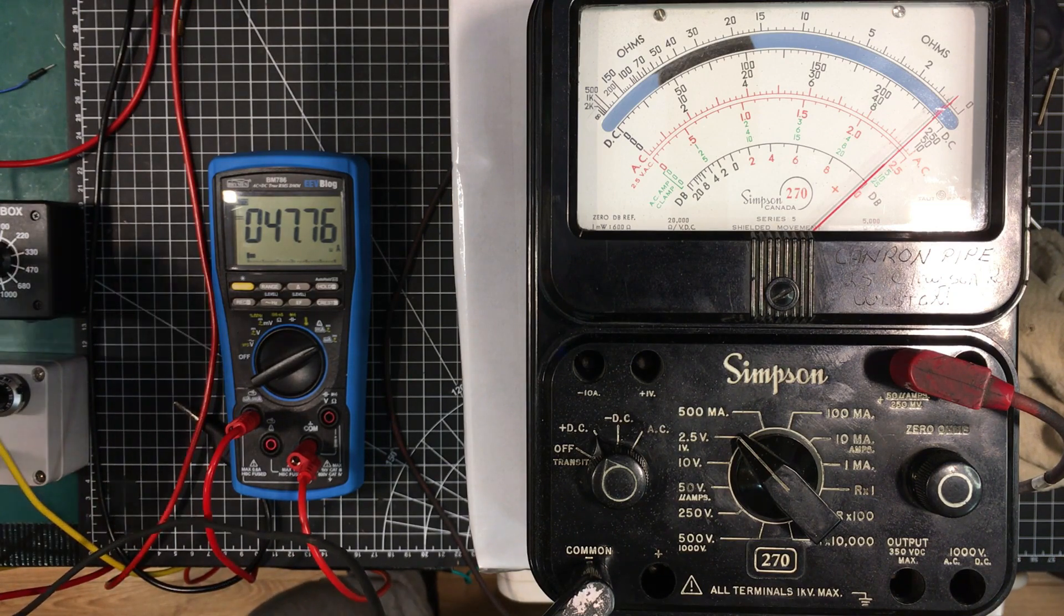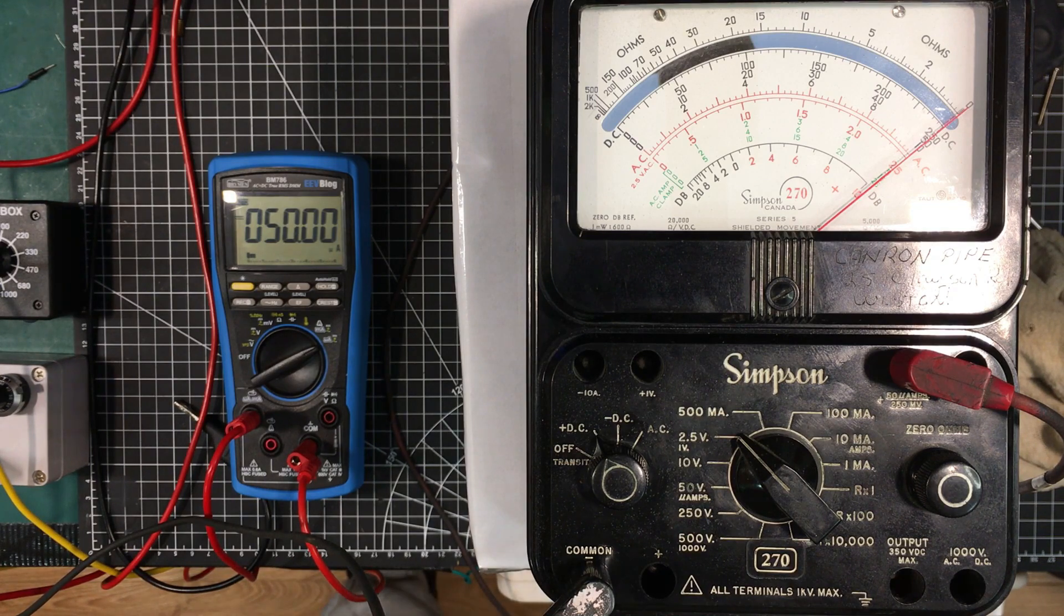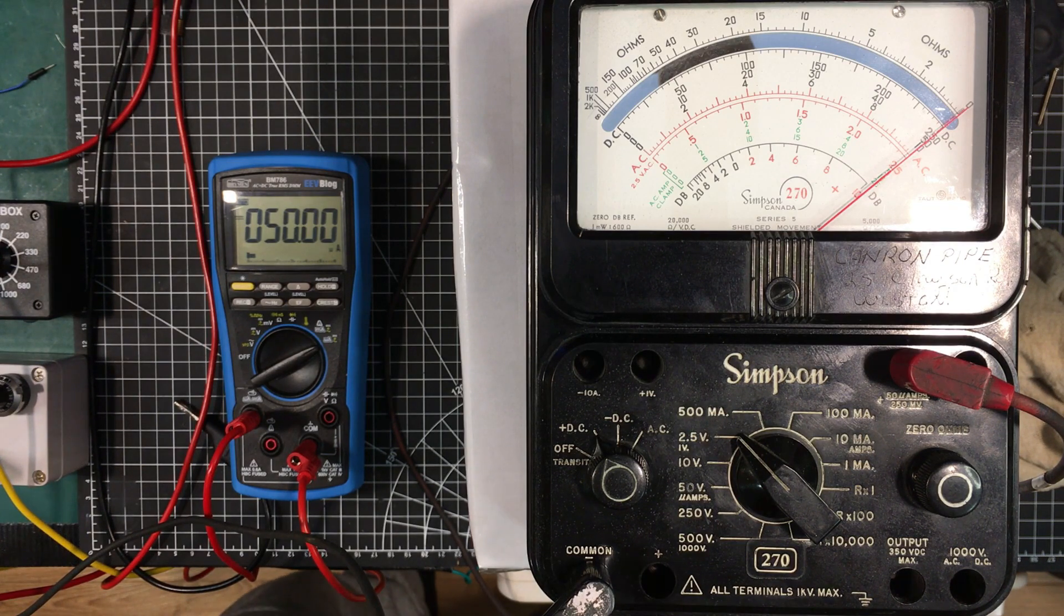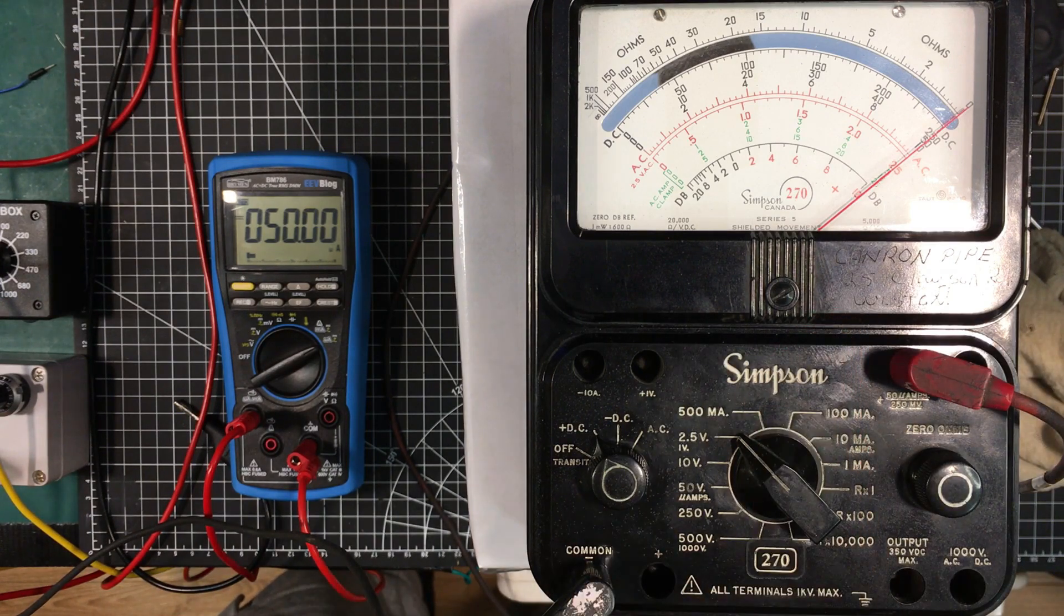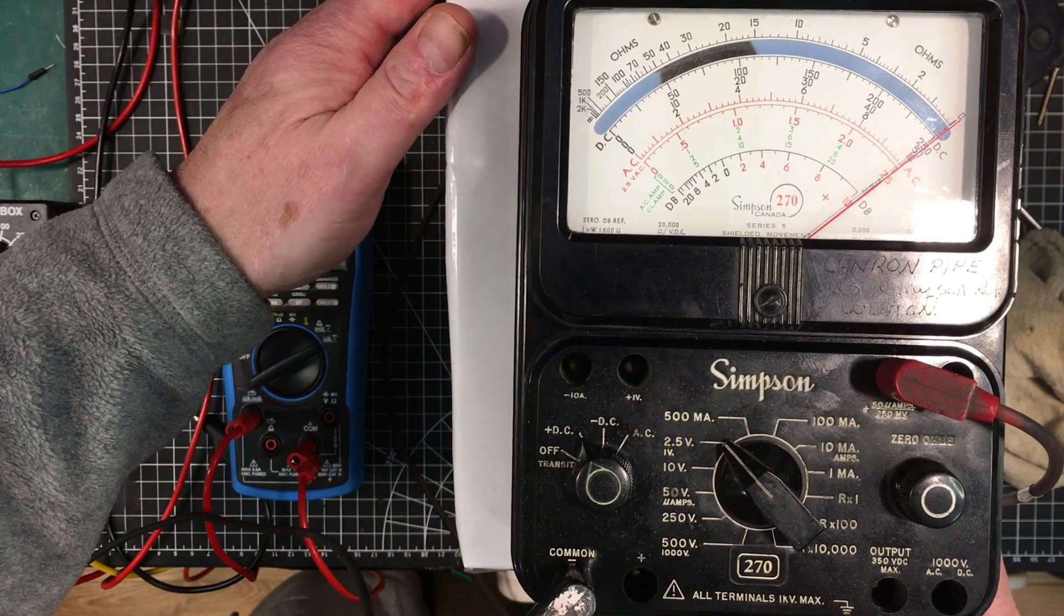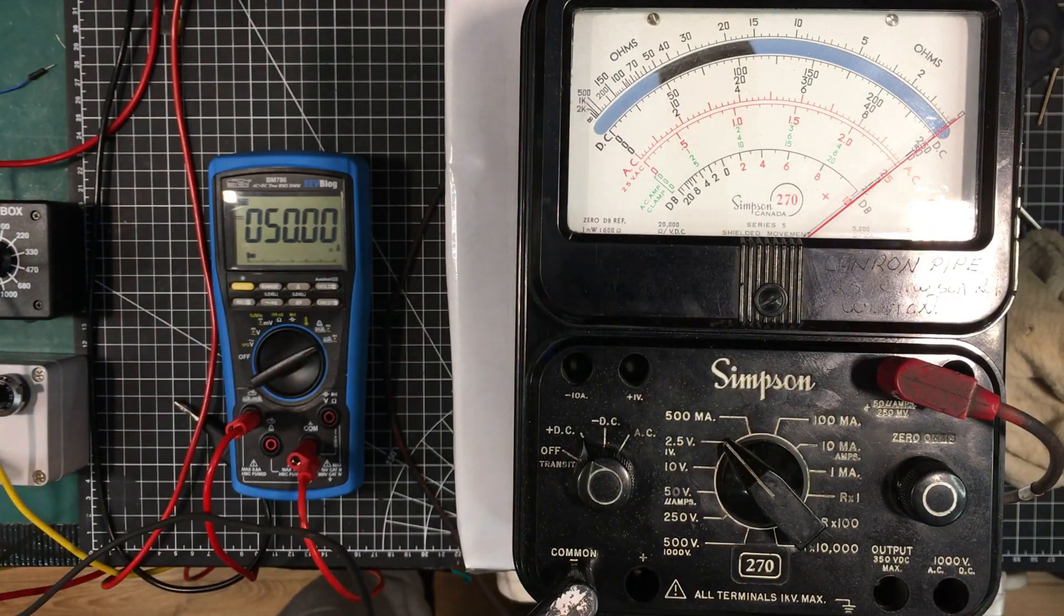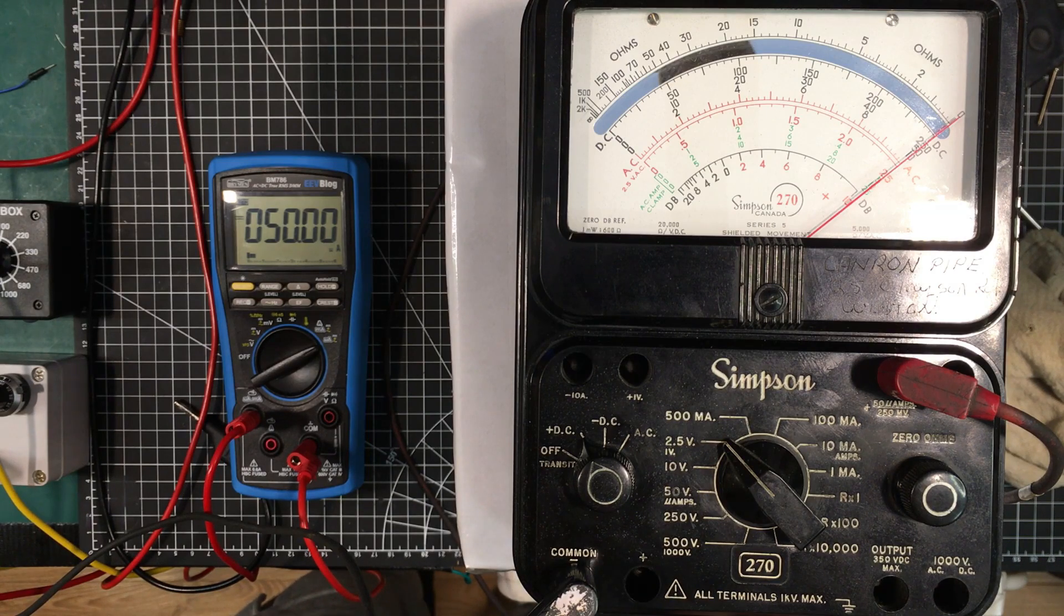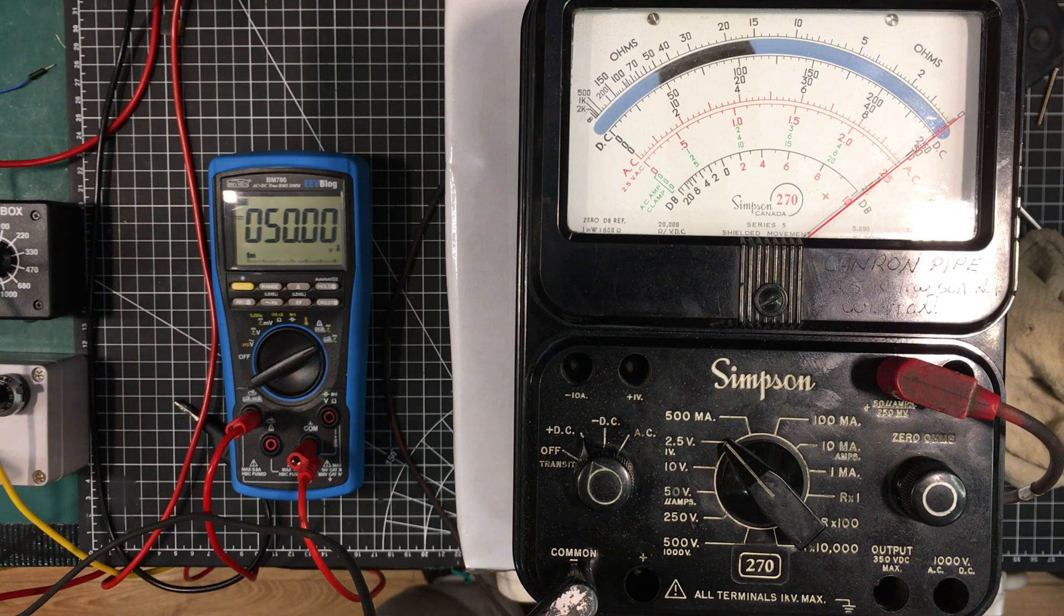Here we have it. We've got exactly 50 microamps shown on the Brymen BM786. I don't know if you guys can see it but I've got the parallax right here. I'm looking at it right now and it's bang on full scale, so I don't need to adjust that at all.